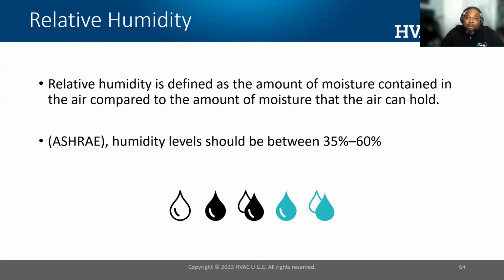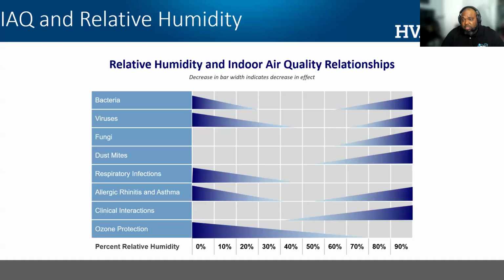The reason we want to keep it in that range is because of the things that can happen if humidity isn't kept in check. We want to keep it between 35% and 60%. In the middle of this chart, we see that bacteria is more prevalent when it's drier, then it drops off, and then it's more prevalent when it's wet. So that range is the best for us. What about viruses? Our business grew significantly during the COVID-19 era, because it was discovered that if it's dry, viruses are more common, and if it's wet, they start to get stronger. So that same area gives us the best.